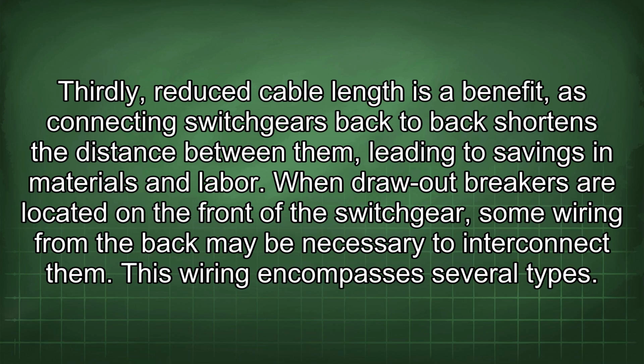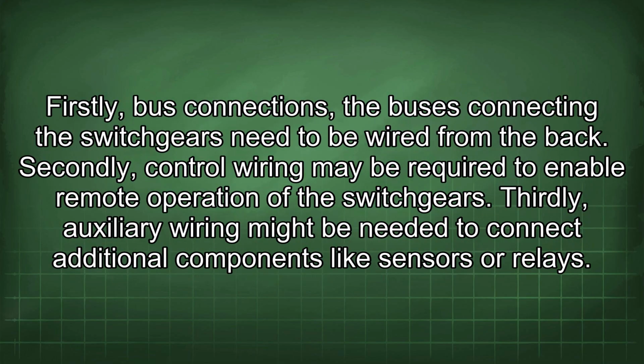materials and labor. When draw-out breakers are located on the front of the switchgear, some wiring from the back may be necessary to interconnect them. This wiring encompasses several types. Firstly, bus connections. The buses connecting the switchgears need to be wired from the back. Secondly, control wiring may be required to enable remote operation of the switchgears. Thirdly, auxiliary wiring might be needed to connect additional components like sensors or relays.